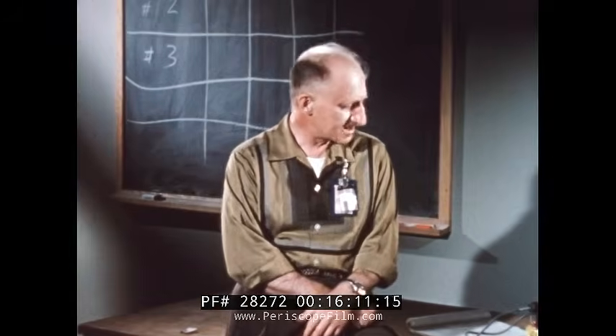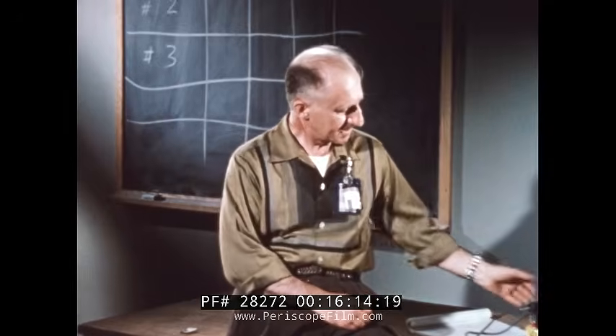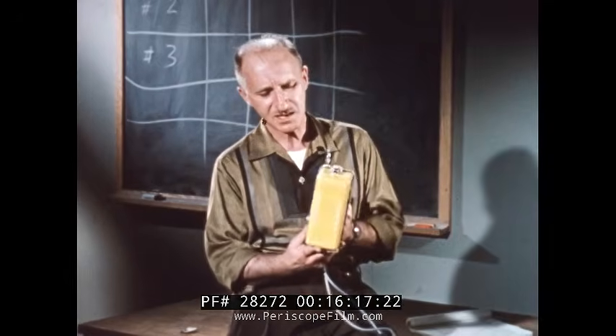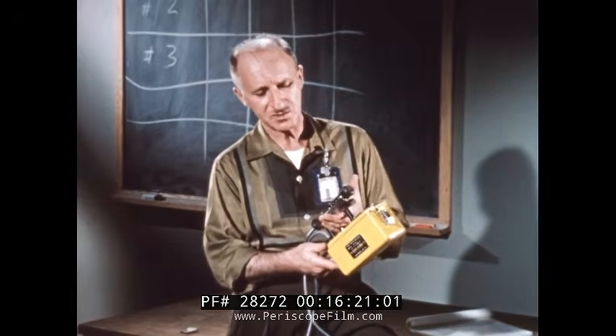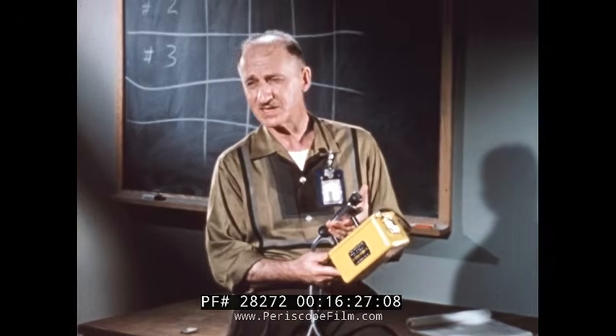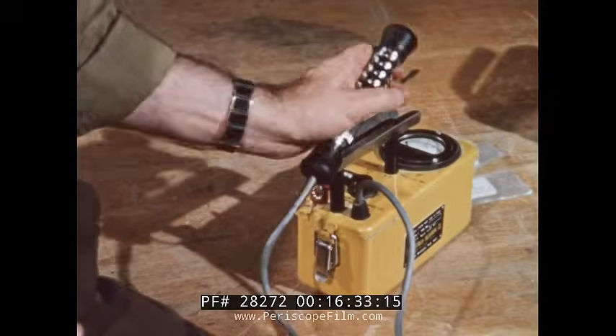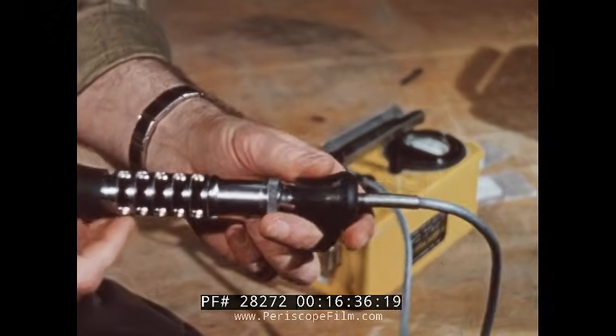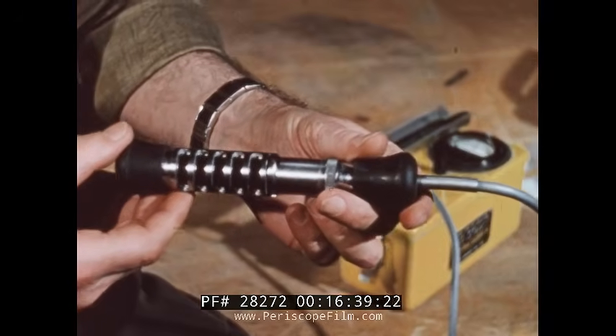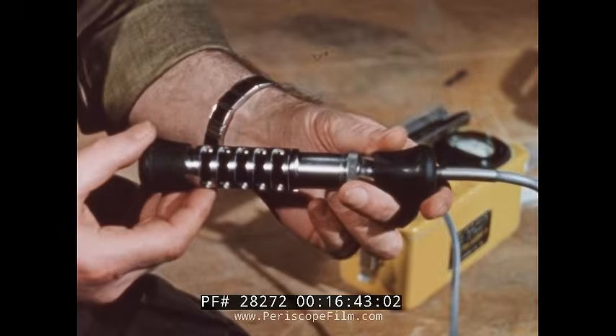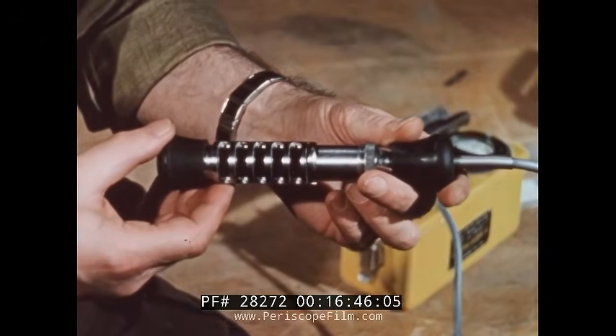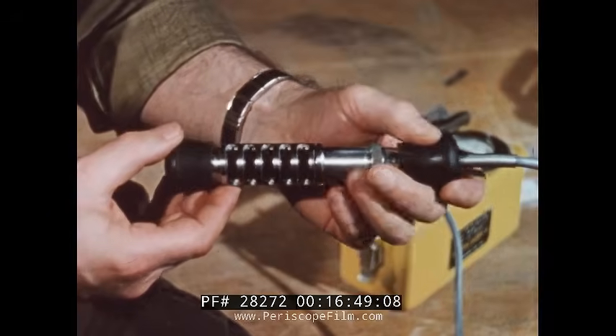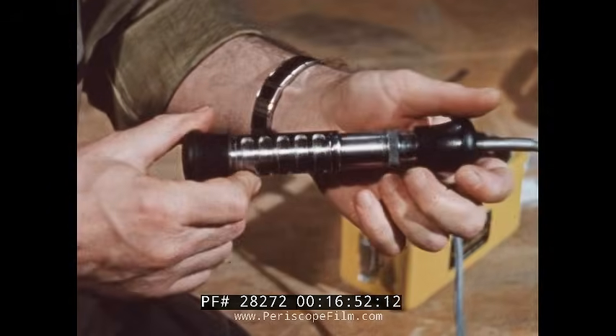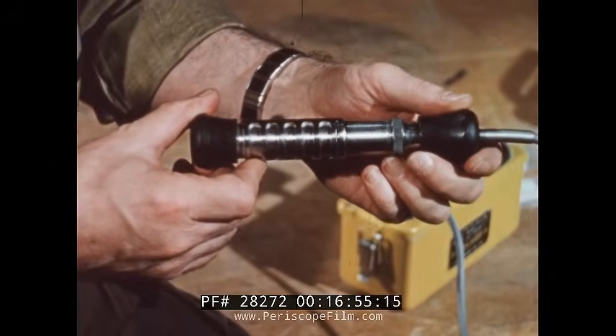The survey meters you'll use here are all multi-range instruments. The CDV 700 is a portable survey meter utilizing a Geiger tube as a detector. It is sensitive to both beta and gamma radiation, but its beta sensitivity is restricted to the moderate and high energy levels. The Geiger tube is encased in a shield. It is gas-filled and detects radiation through the ionization of that gas. With the shield open, it is sensitive to both beta and gamma radiation. By closing the shield on the probe, the instrument becomes sensitive to gammas only.